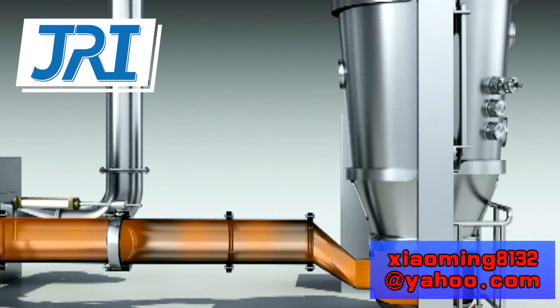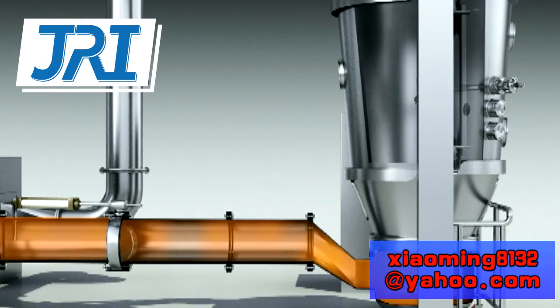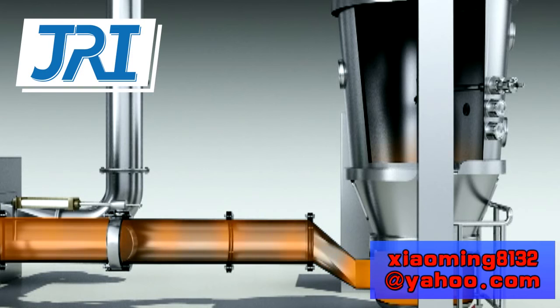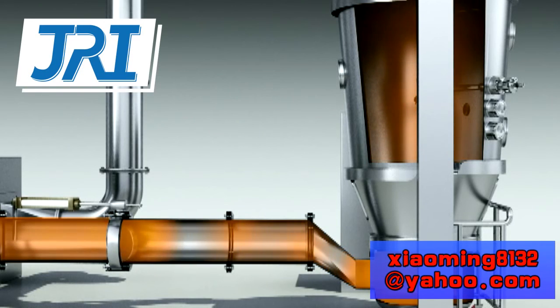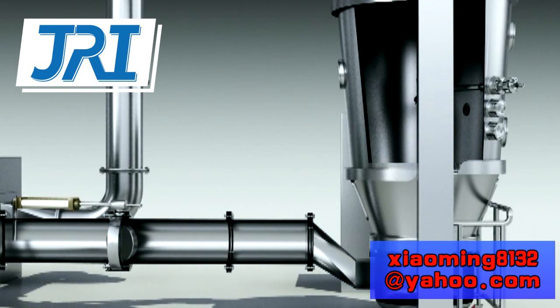Thermostable air speed and humidity transmitters are available on request. They will give the air velocity and humidity just before the air enters into the fluid bed. 4. Pressure differential transmitter or gauge are normally supplied with the air inlet and the exhaust filter, fluid bed, and powder collecting chamber. So to check if there's any blockage or leakage with each section.